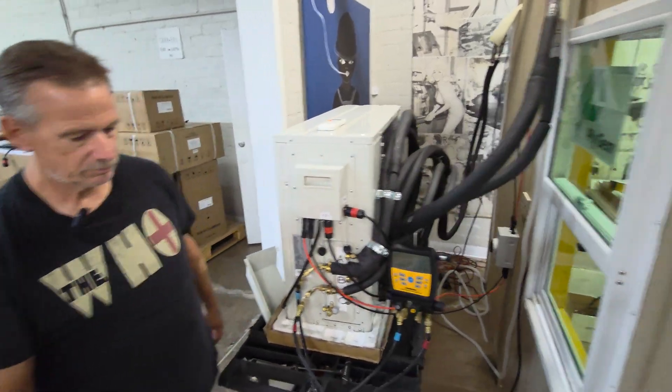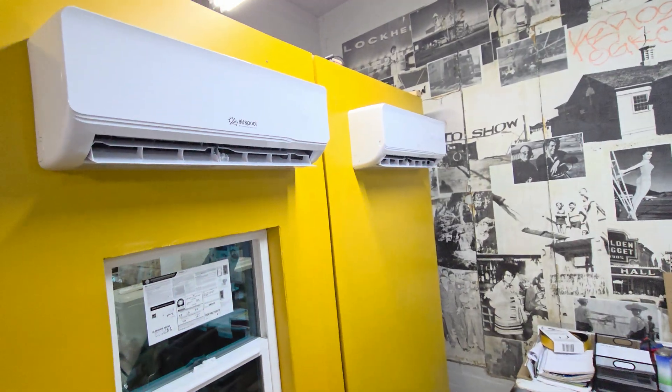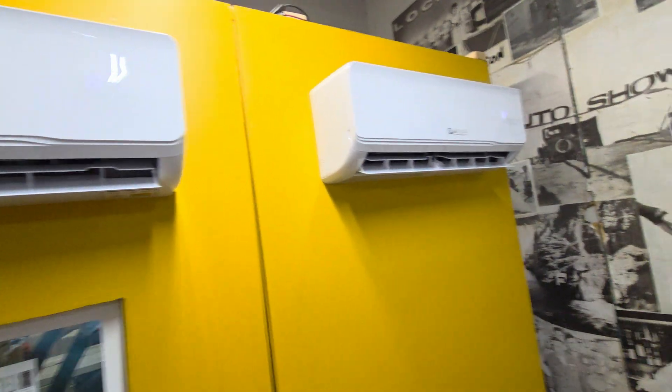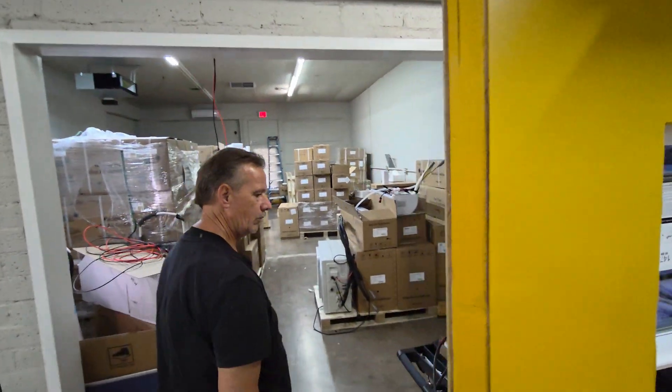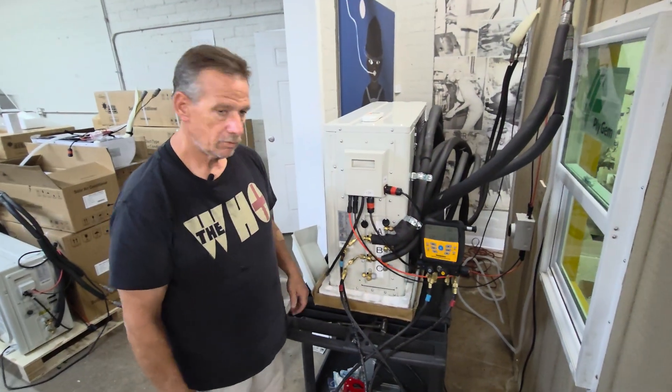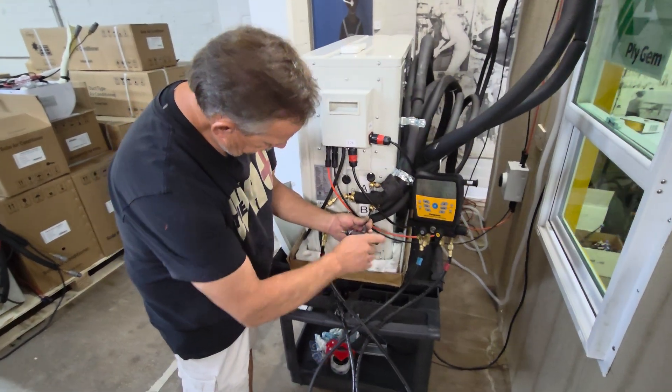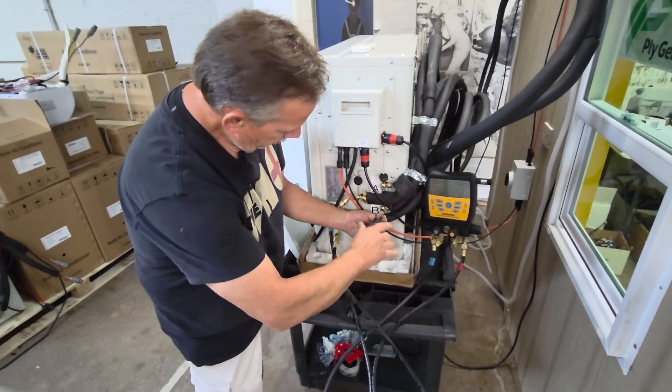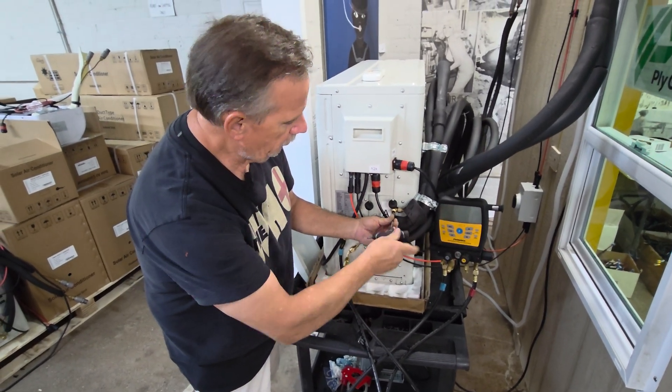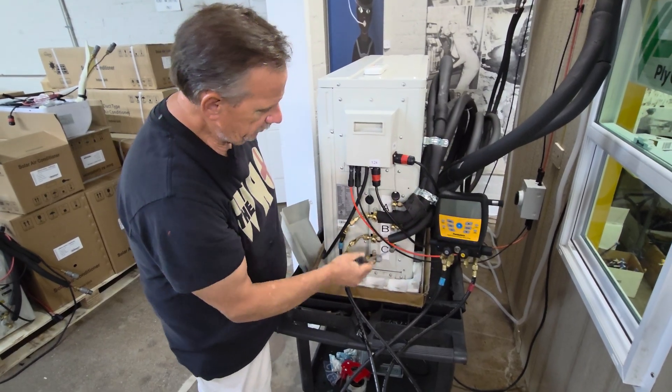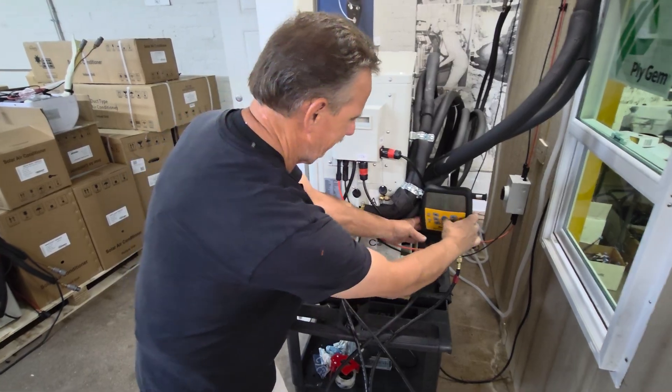Okay, we'll take a look at that. These are the two units we're going to be pumping down, so you have them both set to cooling, 63 degrees and 66 degrees. Make sure they're in cooling and do your stuff. All right, liquid line. So you're closing - it doesn't matter if you're closing B before A. You're going to close the liquid lines, and then these are your suction lines that you'll close when it pumps down to zero.